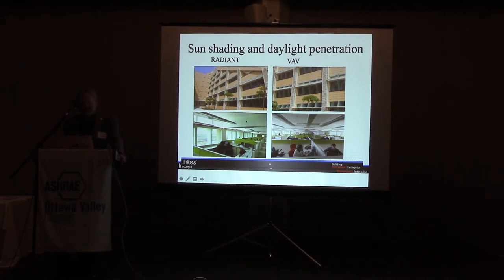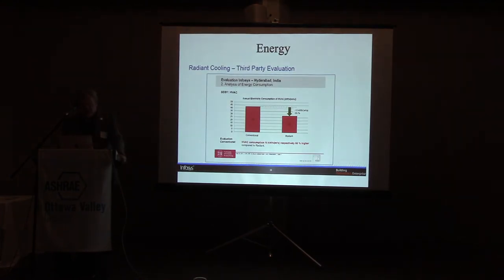Because if you do most of the cooling by a hydronic system, you need much smaller ducts, and you can run them in the hallway. The other thing is, if you don't want the advantage of a higher room but want a standard height, then in a multi-story building you save about 60-70 centimeters of building materials for each story, and that's an economical benefit. So when they measured these two, which, as I said, were both very well designed according to Indian standard, we still had about 30% lower energy use in the building with the radiant system.